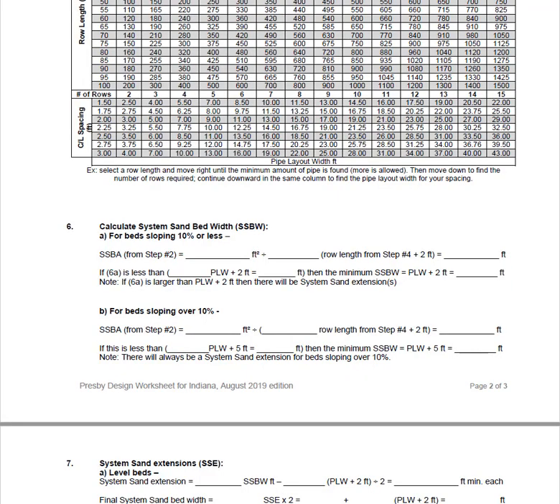Let's calculate our system sand bed width. You will use either option A or B depending upon the slope of the system. This system is level, so we will use option A. We are going to use the system sand bed area from step two — 1,200 square feet — and the chosen row length of 70 feet from step four. We will add 2 feet to our row length, bringing it to 72 feet. Dividing our sand bed area by 72 feet, we end up with 16.7 feet. On the next line, we take our pipe layout width and add 2 feet, which comes to 10.5 feet. Since 16.7 feet is greater than 10.5 feet, we will need system sand extensions.